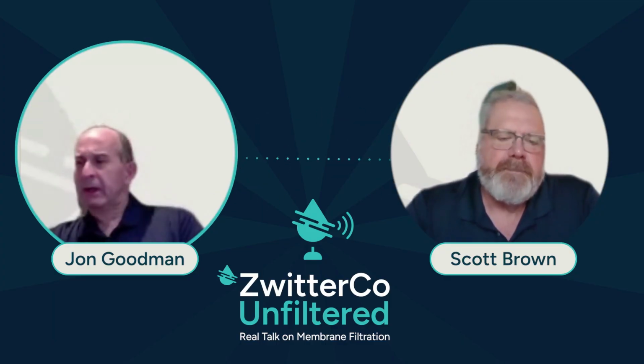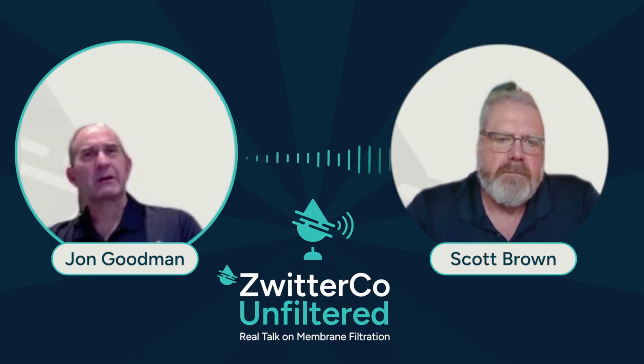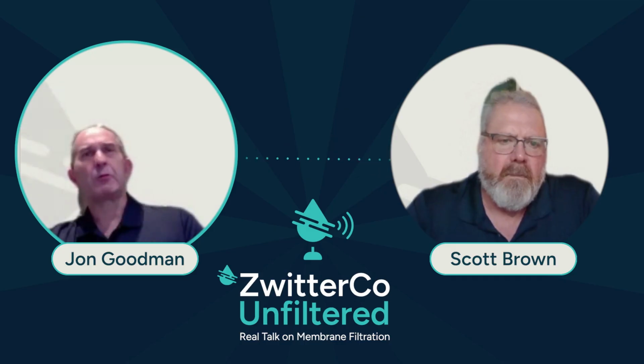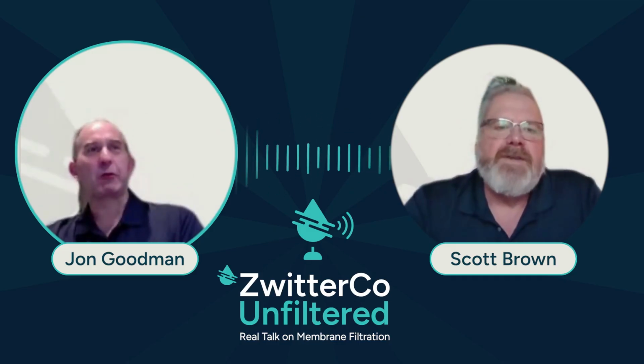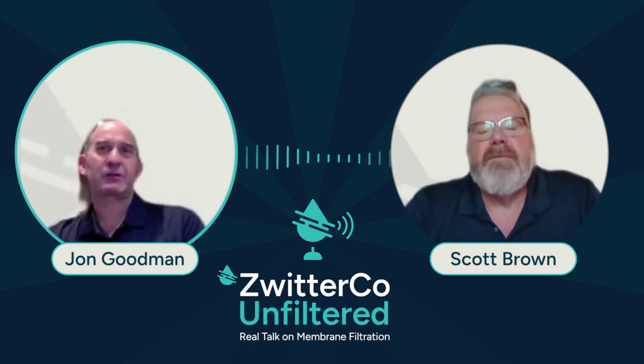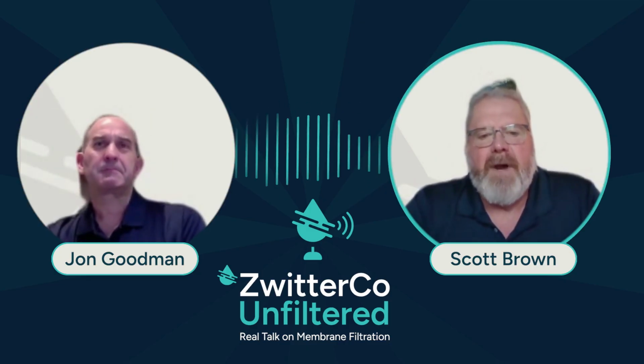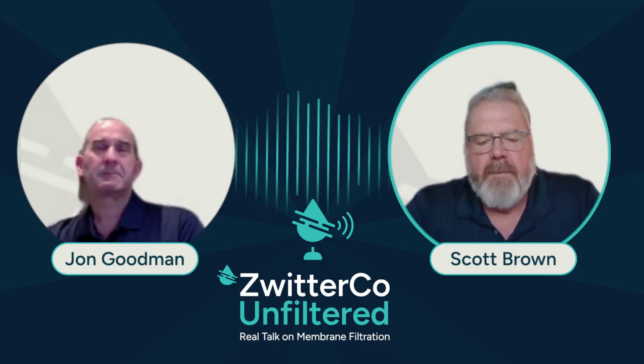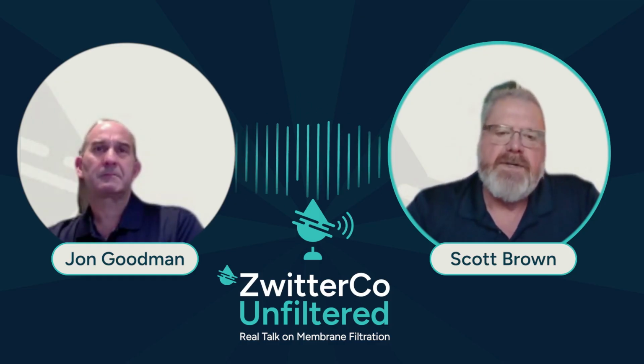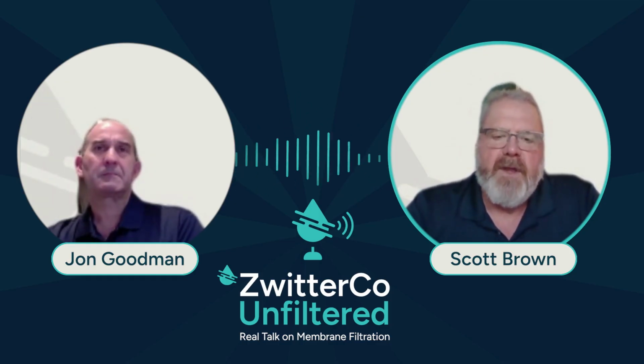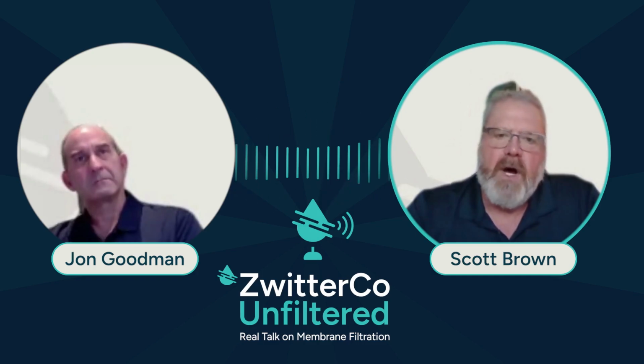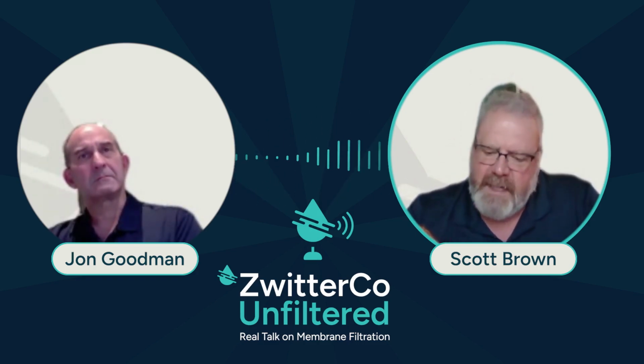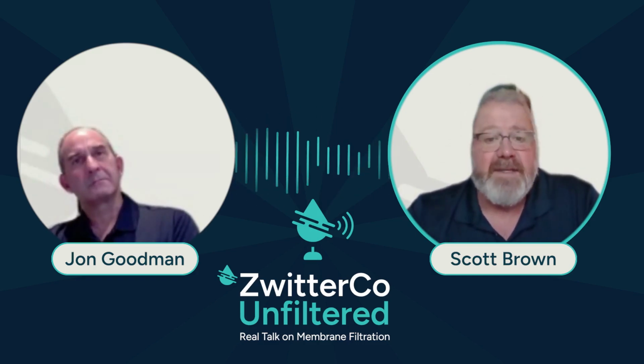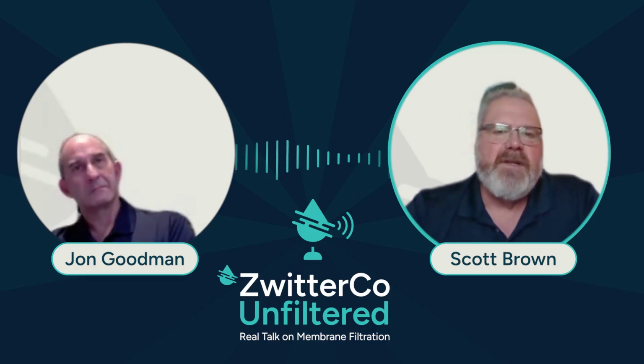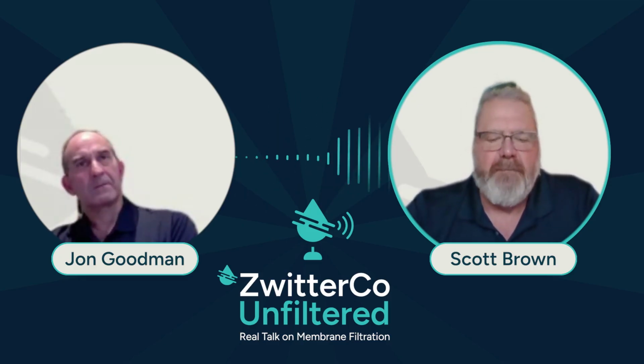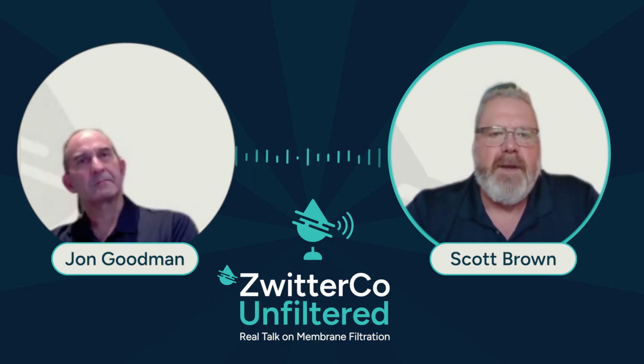From your experience, and actually, I don't know if you covered it, the seal water system, what was the cleaning protocol on that? How were they cleaning, and how are they cleaning the ZwitterCo membranes? So just the membrane system cleaning, they were doing a junk caustic wash, then a full-on caustic wash with caustic and surfactant, then an enzyme wash, then an occasional acid wash, then another caustic wash at the end, and then a sanitize daily. And they were still seeing immense buildup of biofilm on the surface of the membrane.